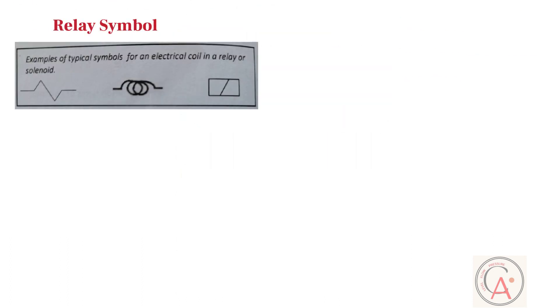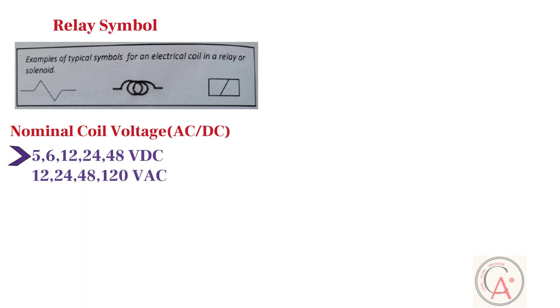As you can see, this is a typical symbol for an electrical coil in a relay or solenoid. Symbols for relays and coils are not as well standardized as for many electronic components. The coils of electromechanical relays have a nominal voltage. Common coil voltages are 5, 6, 12, 24, and 48 volt DC, and 12, 24, 48, and 120 volt AC.